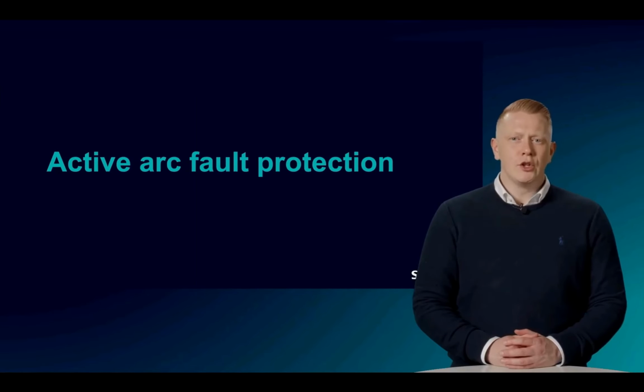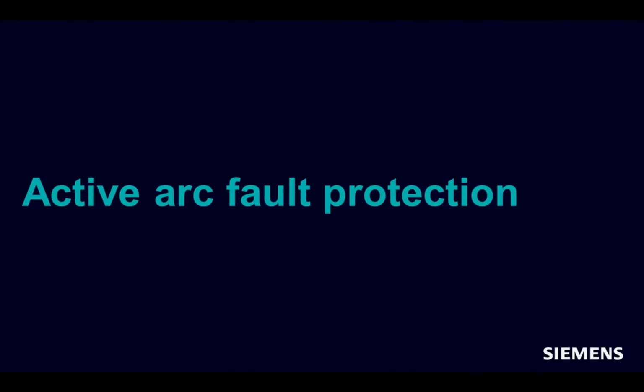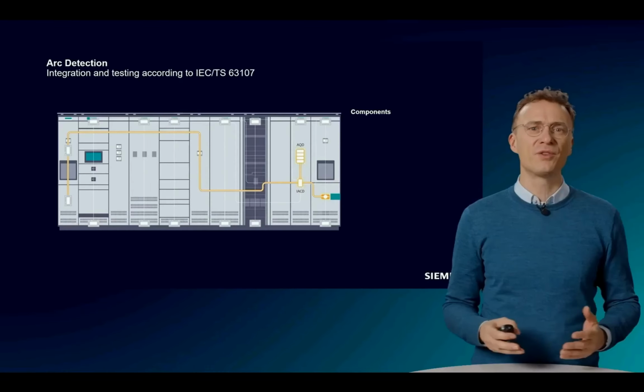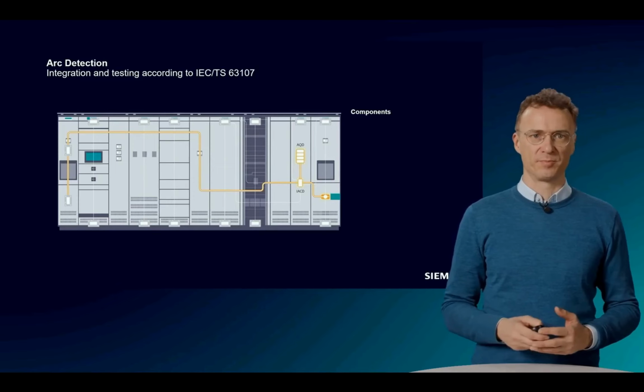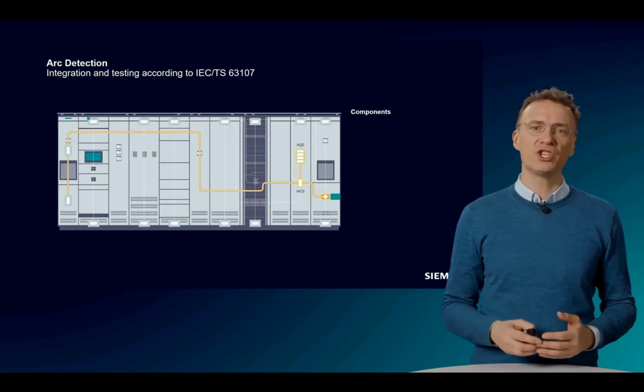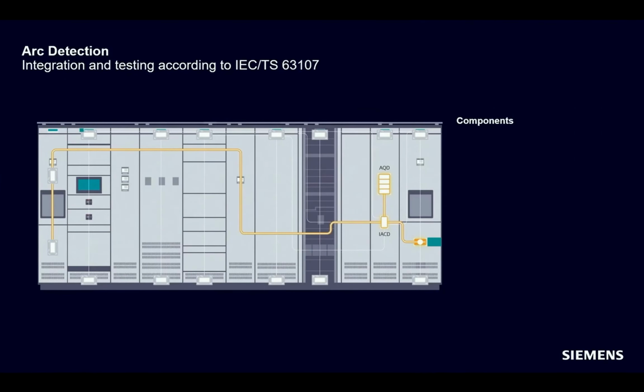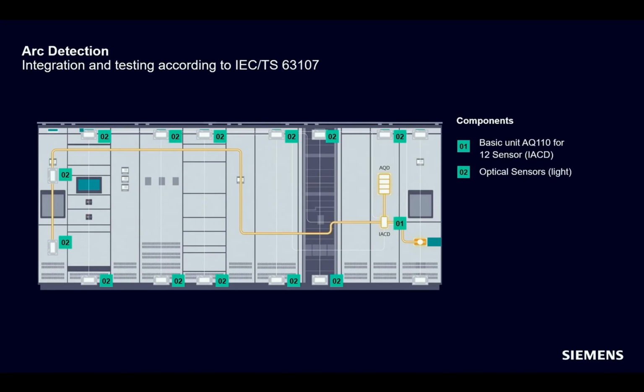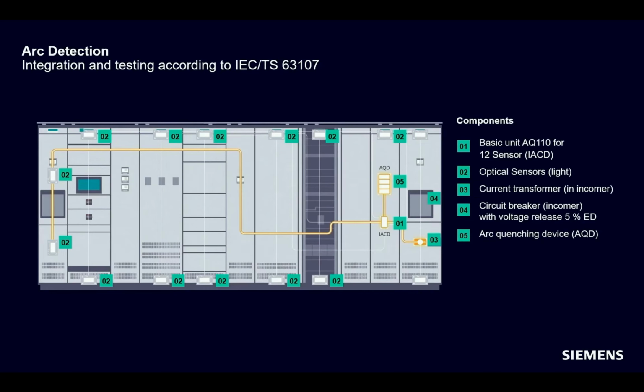In the following, we would like to introduce you to a way to further reduce the tripping time and thus the energy released. In this case, we are talking about an active arc fault protection through an internal arc fault mitigation system, which is integrated according to IEC Technical Specification 63107. Such a system usually consists of a detection relay, light sensors, current transformers, a circuit breaker, and an optional quenching device. More on that in a moment. The light sensors are installed in different areas of the switchboard and monitor for the occurrence of light emission from an arc fault. If a light event is detected, a signal is sent to the detection relay. This sends a trip signal to the circuit breaker of the incoming feeder. It opens and the arc extinguishes.